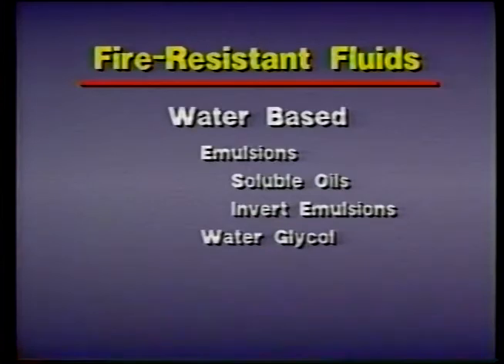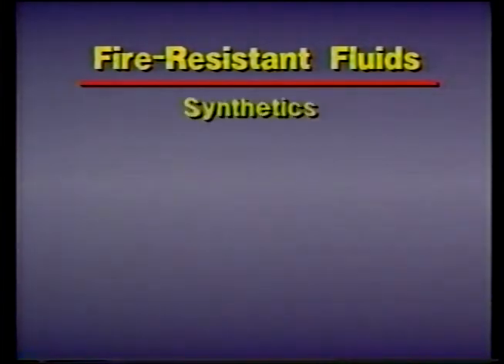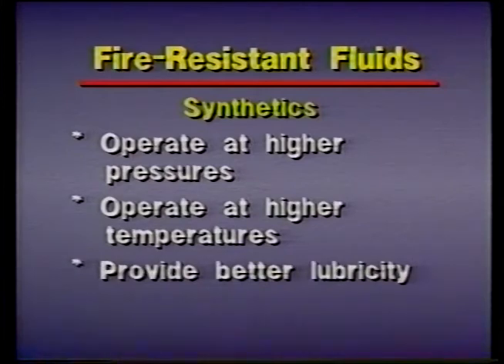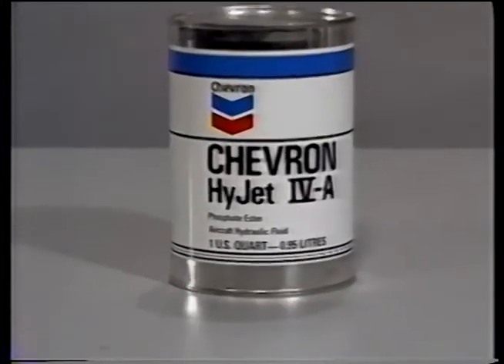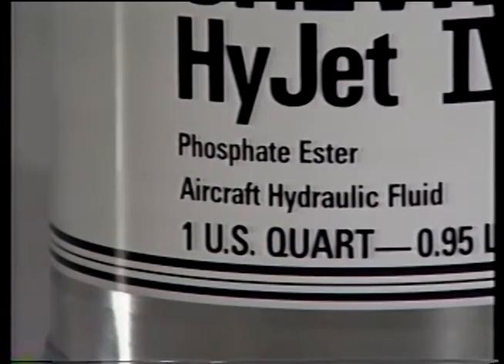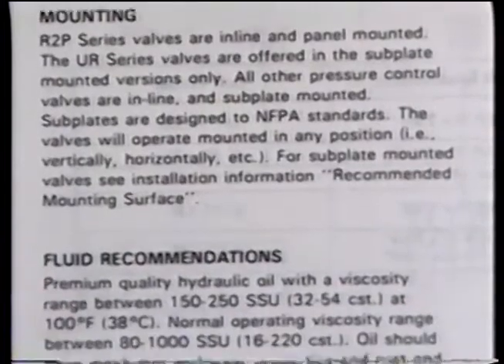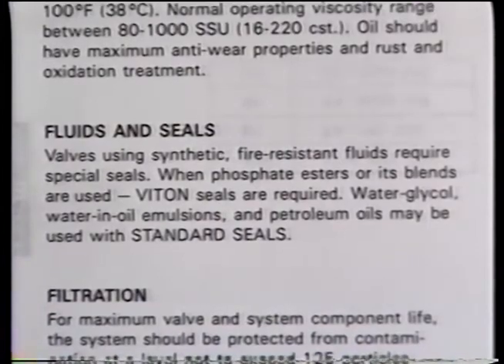The last category of fluids we need to discuss are the synthetic fluids. These man-made solutions operate at higher pressures and higher temperatures. They provide better lubricity and in many instances are more fire resistant than emulsions. They do however cost more than most water-based fluids. One common synthetic fluid is phosphate ester, often used in high pressure systems where fire resistance is needed. If you plan to use a synthetic fluid, you need to make sure your system is compatible with the specific fluid you intend to use — this will save you downtime later on.